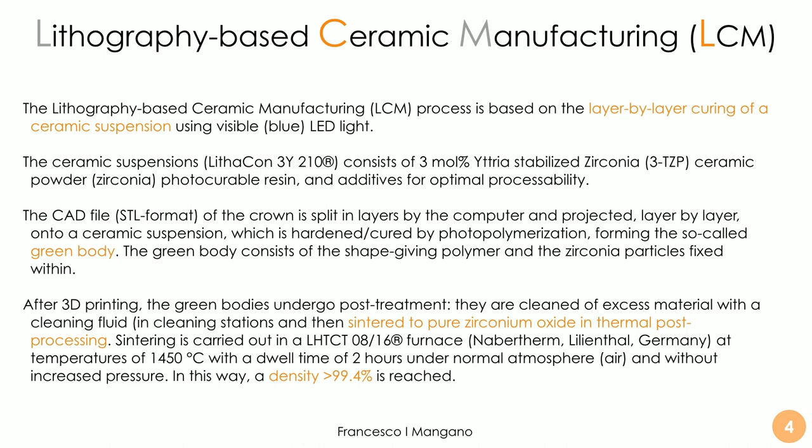The 3D printing process is based on layer-by-layer curing of a ceramic suspension. The ceramic suspension for zirconia is called LithaCon 3Y 210 and consists of a 3% mole yttria-stabilized zirconia ceramic powder with photocurable resin and additives. For lithium disilicate the product is different. The crown or bridge file is split into layers by the computer, and these layers are projected layer by layer onto the ceramic suspension, which is hardened by photopolymerization.